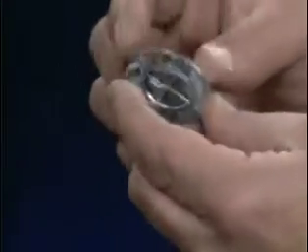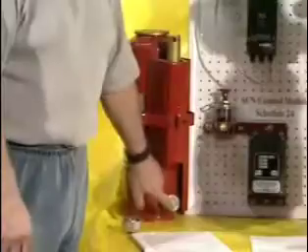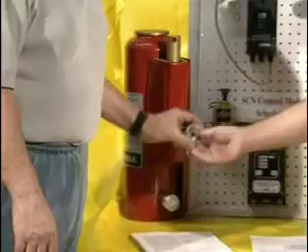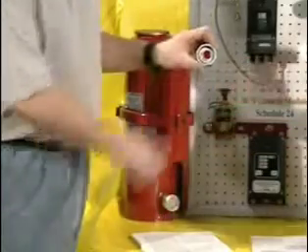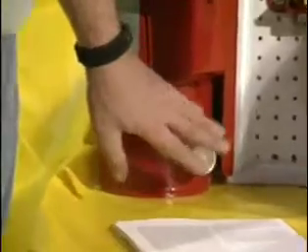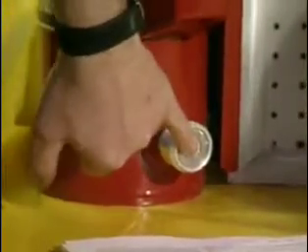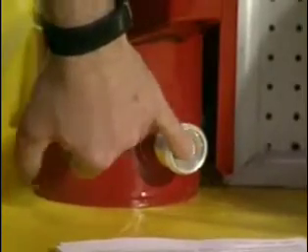Now, isn't there a plastic ring? Right here on the outside there's a plastic ring. So it needs to be against this fitting? Against this shoulder right here. Prevents it from falling out. These need to be changed on a semi-annual basis. These burst disc unions need to be pulled out. They need to make sure that orifice is clean.